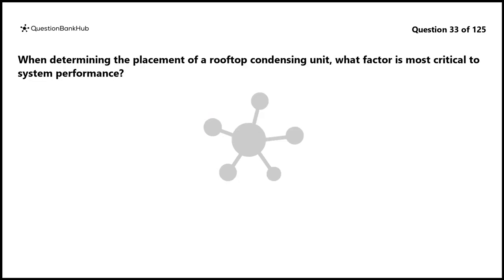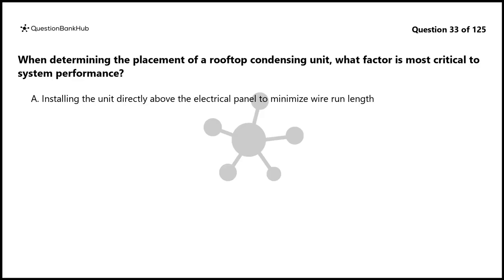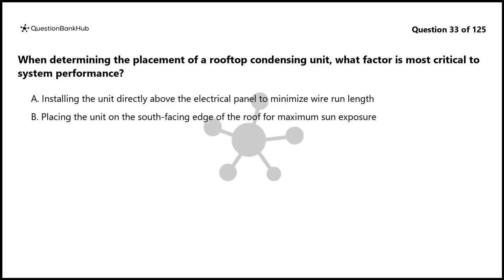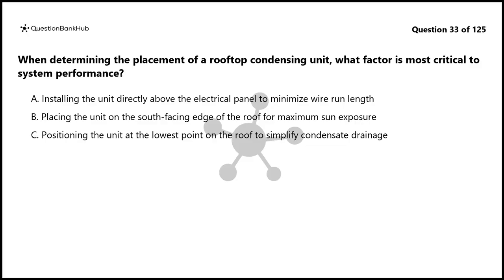Question 33. When determining the placement of a rooftop condensing unit, what factor is most critical to system performance? A. Installing the unit directly above the electrical panel to minimize wire run length. B. Placing the unit on the south-facing edge of the roof for maximum sun exposure. C. Positioning the unit at the lowest point on the roof to simplify condensate drainage. D. Ensuring adequate clearance around the coil for unrestricted condenser airflow.